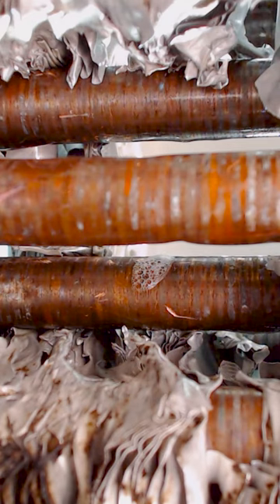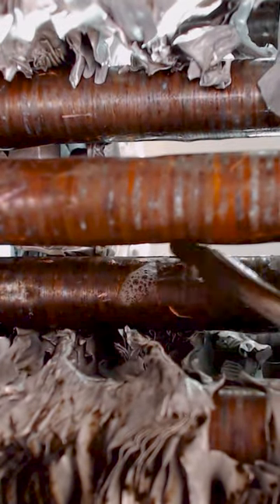You can see this tool found a leak that is extremely small, so even when you add bubble leak detector on it, it's only really foaming.